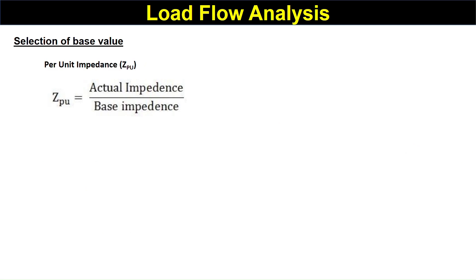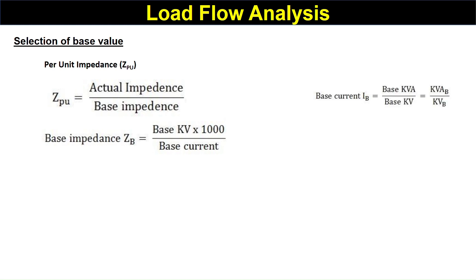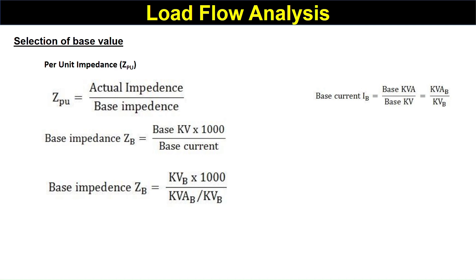Per unit impedance is the ratio of actual impedance divided by the base impedance. Base impedance equals base voltage multiplied by 1000, divided by base current. Substituting base current as base power divided by base voltage, and rearranging, the base impedance becomes base voltage squared multiplied by 1000, divided by base power.